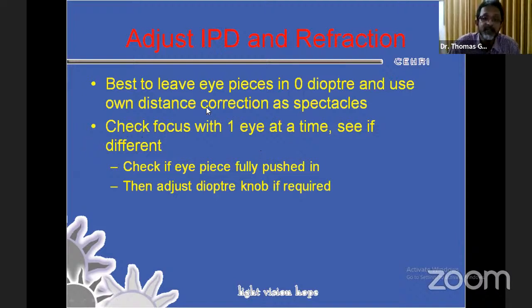Anyway, after that you check focus one eye at a time, and if it's different, check if the eyepieces are fully pushed in. One may be pulled out a little bit or unscrewed a little bit, so they may be at two different planes. That's the first thing to check. If that's not it, there's something wrong with the optical elements in the eyepiece, get it serviced, but in the meantime, you can adjust the diopter knob and focus one eye at a time.